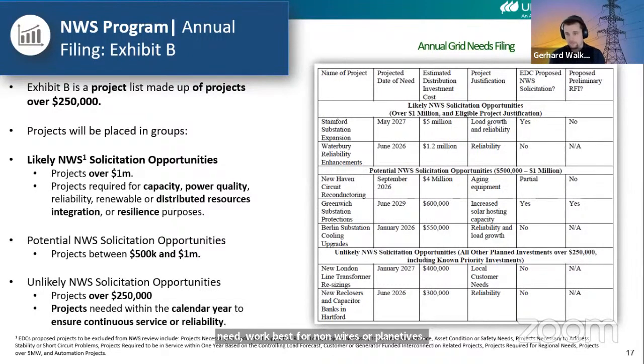It's also highly dependent on the technology. I'm sorry if I'm picking on batteries a bit, but especially for batteries there's running costs of the systems, maintenance, and life expectancy compared to a traditional upgrade. A normal transformer lasts 40 to 60 years, a battery 12 to 20. That's why we always talk about deferral — the maximum deferral is the lifespan of the NWA asset, which is typically shorter than that of the traditional asset, and at that point we'd have to reevaluate.